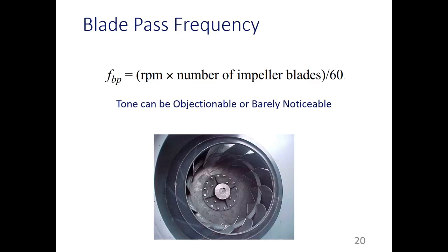So here's that blade pass frequency equation. The blade pass frequency is just the RPM, so you have revolutions per minute times the number of impeller blades. And then you divide by 60, so you end up getting it per second. If we're doing revolutions per minute times the number of blades divided by 60, then every time a blade passes by, however many times it does that within a second, that's the frequency the blade pass frequency is going to be at. And like I said before, this tone can be really objectionable or barely noticeable.